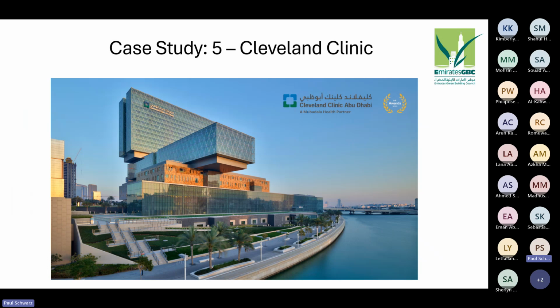That was in Saudi Arabia. Cleveland Clinic will be the last case study I bring up. This was an interesting project with more than 22 extremely large diesel generators in the basement of the building. The design brief required that the hospital work 24 hours a day, and the diesel generators might kick in during a brownout or reduction in electrical capacity. The hospital needed to be 100% operational off these 22 generators for up to a month if strictly necessary, not just basic life safety systems.